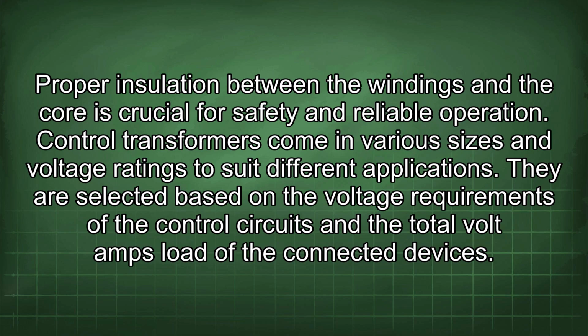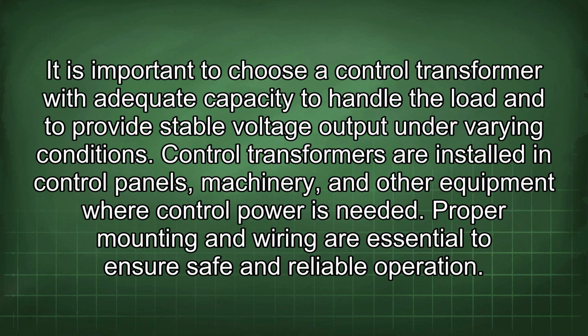Control transformers come in various sizes and voltage ratings to suit different applications. They are selected based on the voltage requirements of the control circuits and the total volt amps load of the connected devices. It is important to choose a control transformer with adequate capacity to handle the load and to provide stable voltage output under varying conditions.